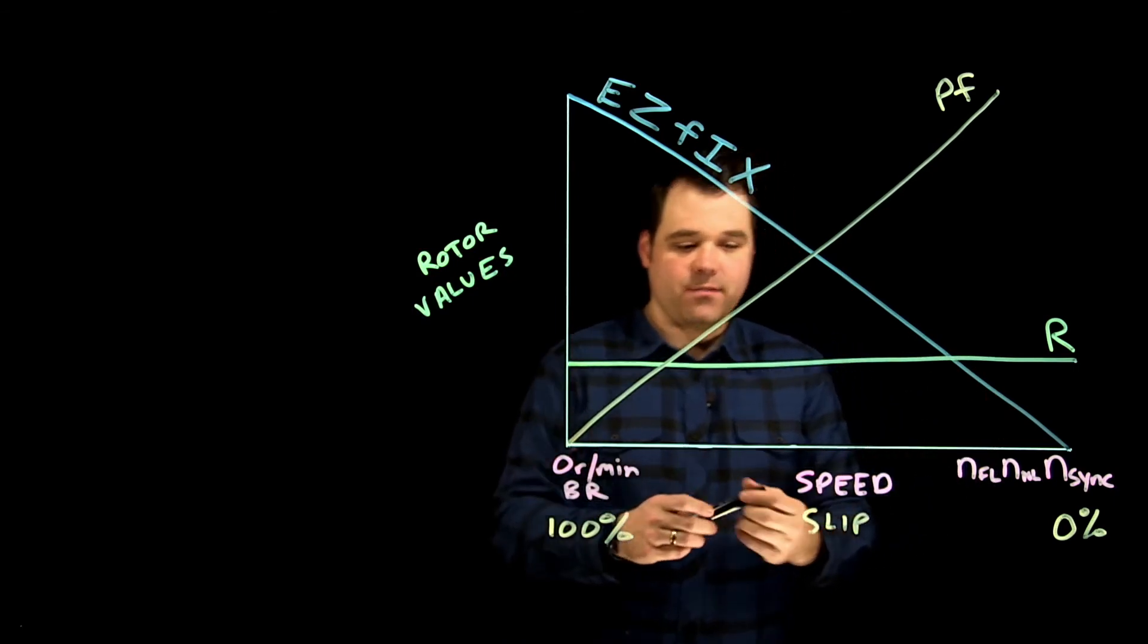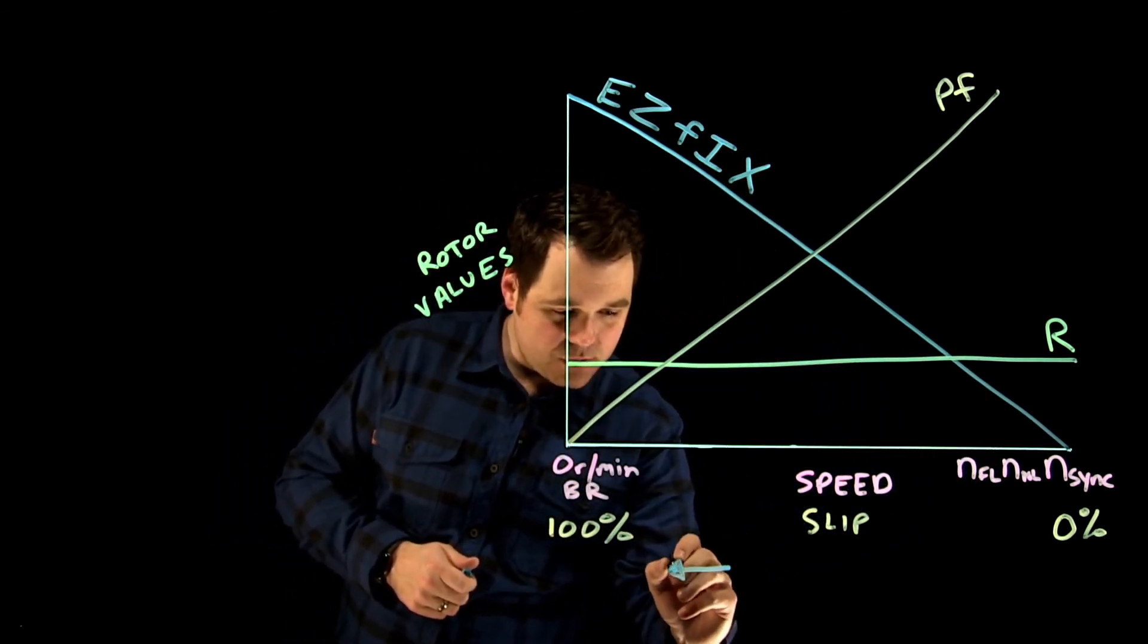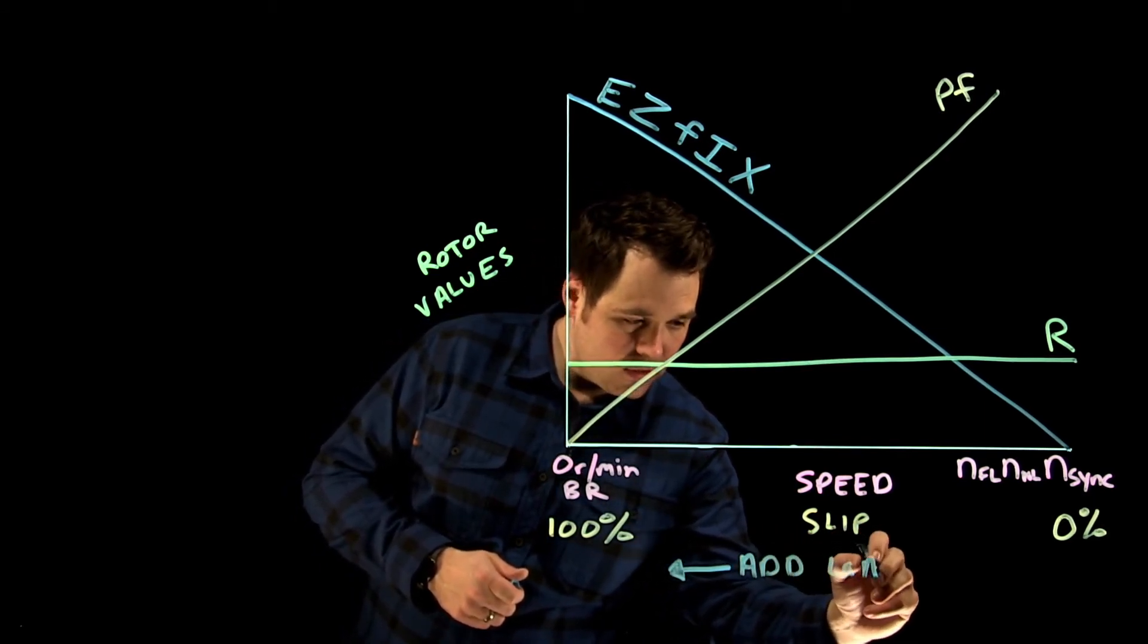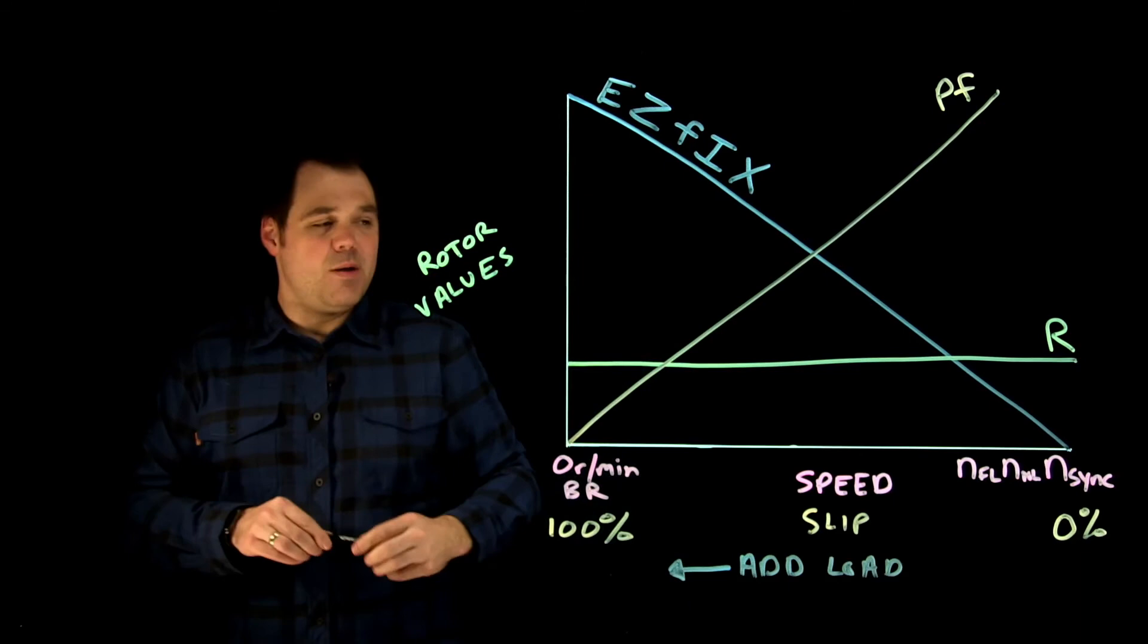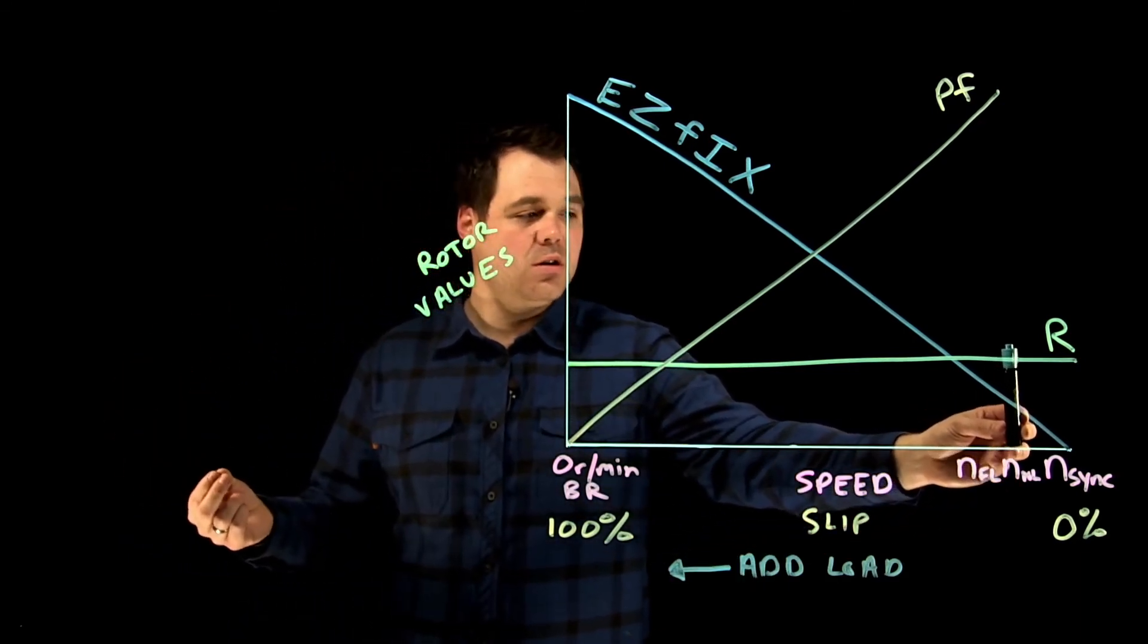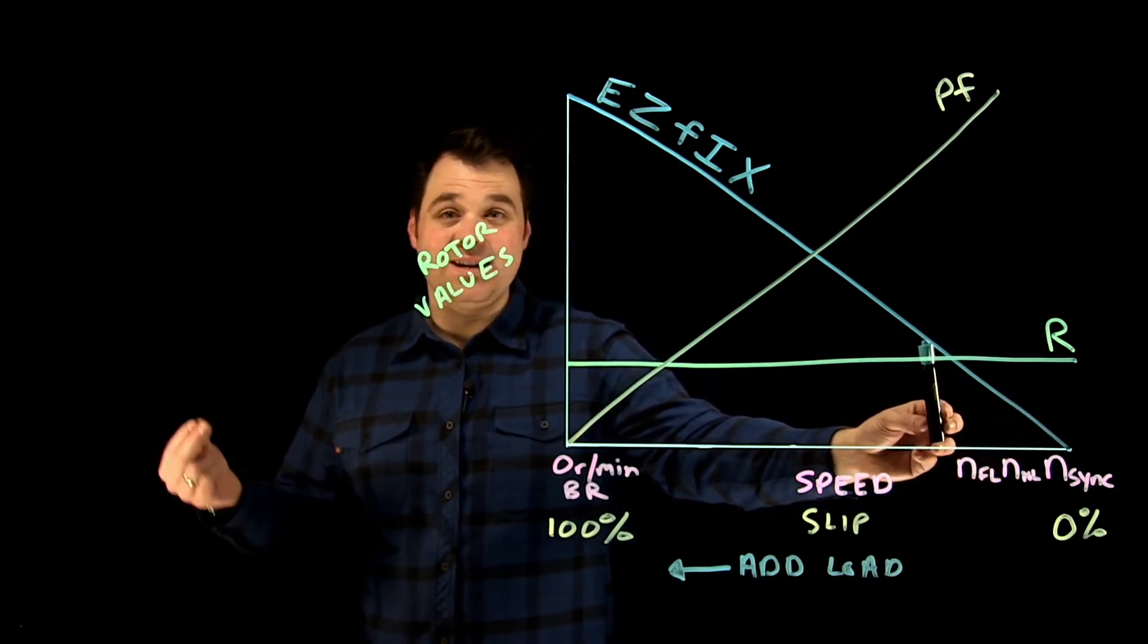Think about that. If I add load, I'm going to shift this way on the chart. Add load. So maybe I'm running at a no load speed over here, I start to add a little bit of load, my speed is going to slow down, my slip is going to increase.